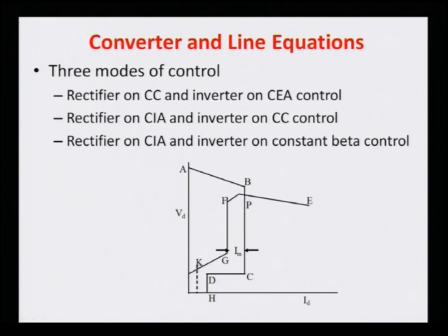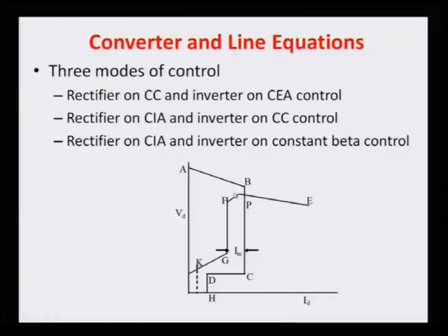But due to a change in the voltage, or limiting, or problems on the AC and DC sides, for example a huge voltage drop when your OLTC is exhausted, the characteristic can shift. So, we have another characteristic. You can see the rectifier is working here, and the inverter is working in the constant current controller, because the voltage can fall here, and we can get various characteristics, intersecting somewhere on this axis FG.